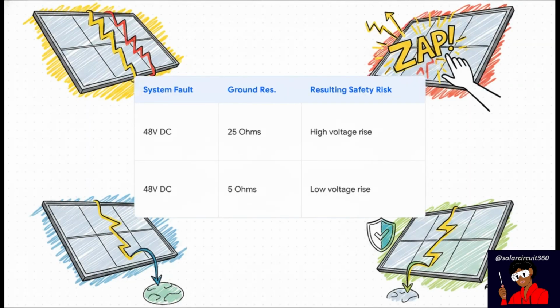To answer that, let's look at the terrifying reality of something called voltage rise. Imagine a 48-volt DC fault hitting a totally compliant 25-ohm ground. Because that resistance is relatively high, the voltage essentially backs up and elevates your entire grounding system. Suddenly, the metal frames of your solar panels are carrying that voltage, creating a lethal touch voltage shock hazard. If you touch the frame, you complete the circuit. Yikes. But if that exact same 48-volt fault hits a highly efficient 5-ohm ground, the voltage rise is incredibly low. The fault clears quickly, and the touch risk is minimized. So yeah, 25 ohms might be legally compliant in some areas, but lower is always, always better.